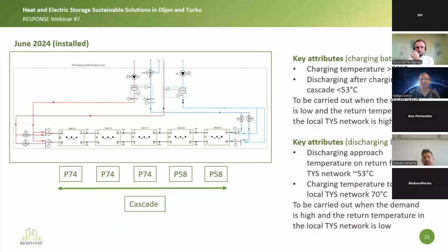Effectively back to the original thought we would have, which is a cascade solution consisting of 3 P74 degree materials, changing phase at 74 degrees centigrade, and 2 P58 degree materials, changing phase at 58 degrees centigrade. When demand is low, we charge up the batteries, and when demand is high, we discharge the batteries into the flow of the network. It's a very simple system, with no heat pumps or mechanical systems other than a few pumps and valves.